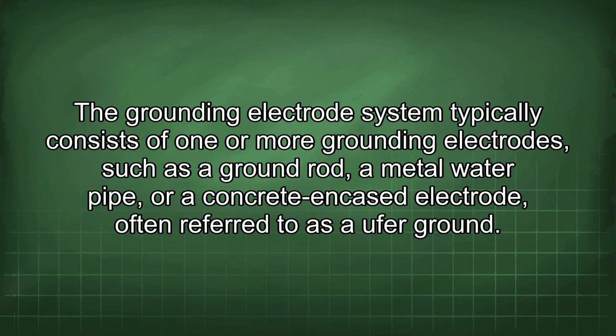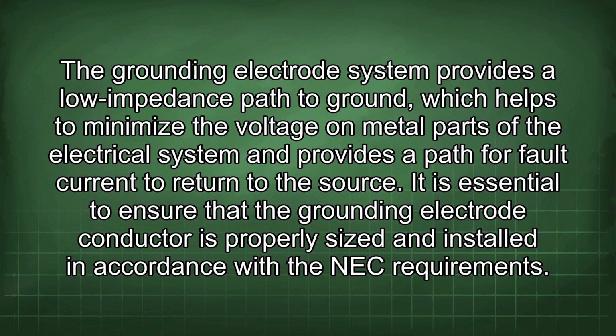The grounding electrode system typically consists of one or more grounding electrodes, such as a ground rod, a metal water pipe, or a concrete encased electrode, often referred to as a Ufer ground. The grounding electrode system provides a low impedance path to ground, which helps to minimize the voltage on metal parts of the electrical system and provides a path for fault current to return to the source.